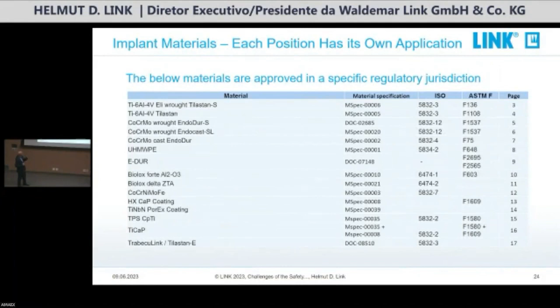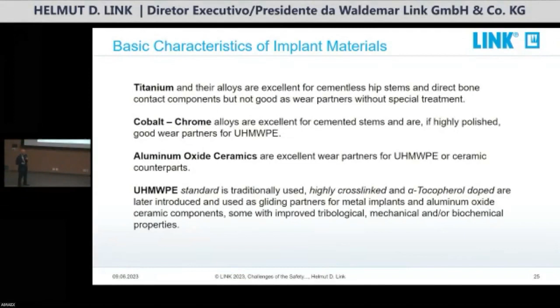Now, in general, titanium and its alloys are excellent for cementless hip stems and direct bone contact components, but not as good for wear partners. Cobalt chrome alloys are excellent for cemented stems and, if highly polished, are good wear partners for poly. Aluminum oxide ceramics are excellent wear partners for poly or ceramic counterparts. And the poly, again, is divided into traditional poly, highly cross-linked poly, and alpha tocopherol or vitamin E doped poly, which was introduced much later but is nowadays a very popular poly, because the vitamin E grabs the free radicals, the oxygen, and at least prolongs the life, to be careful in statements, prolongs the life of the poly.